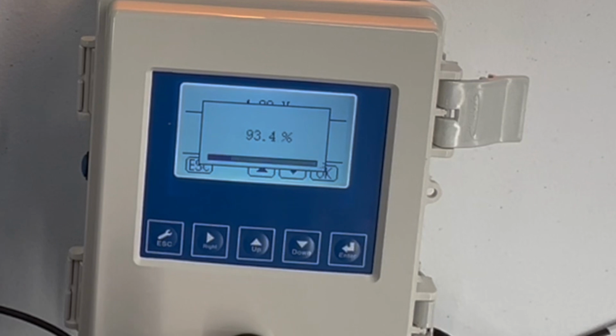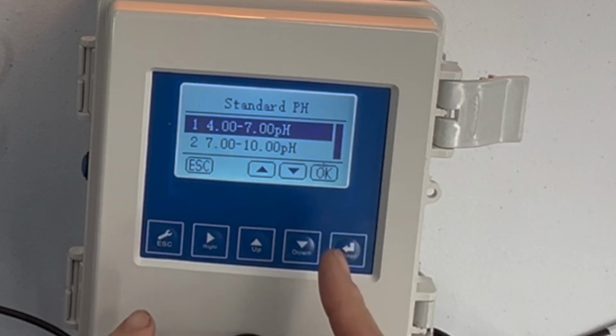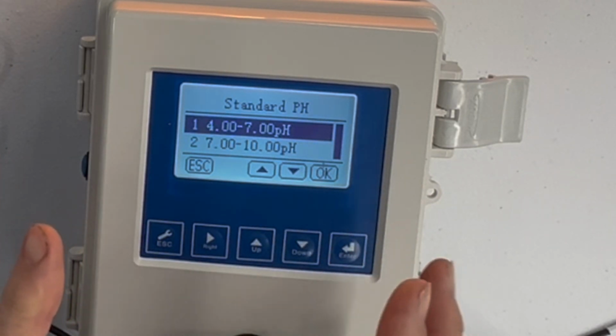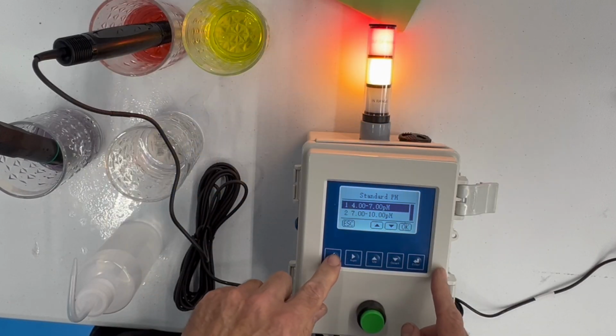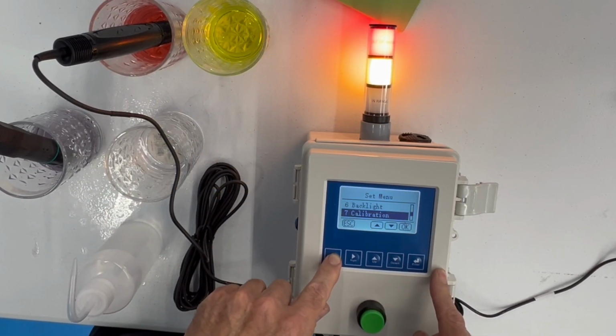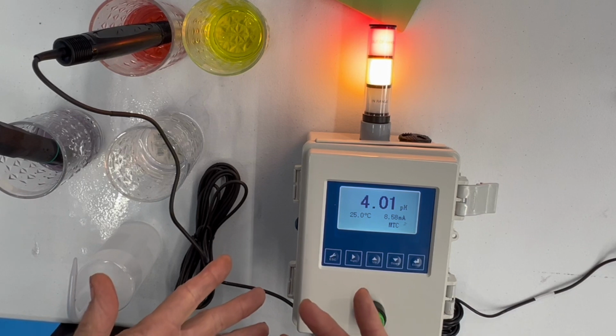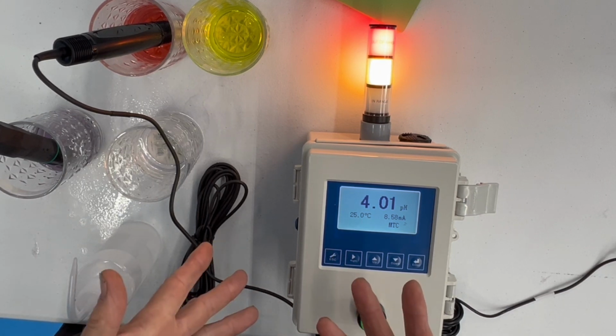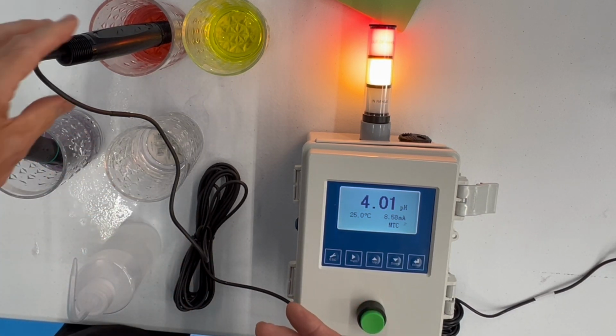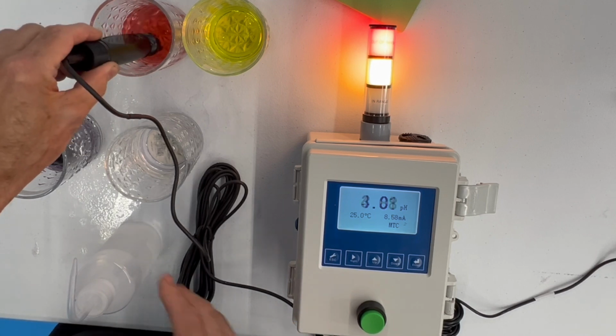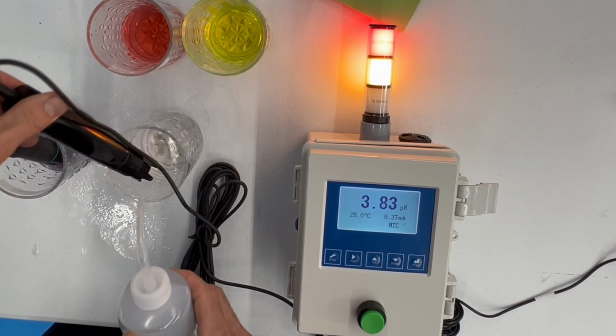And now we can check and see what we've got. So 93.4%, that's not a great number. We really want to see better than that, but just for the purposes of illustrating the calibration, it's good enough. So 4.01 in a 4 buffer, that's perfect. And now we'll just see what it reads in the 7 buffer.